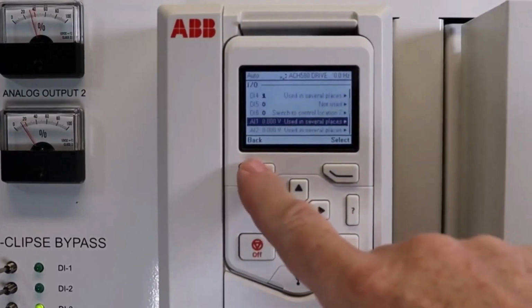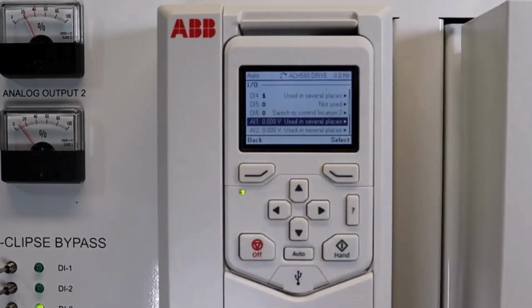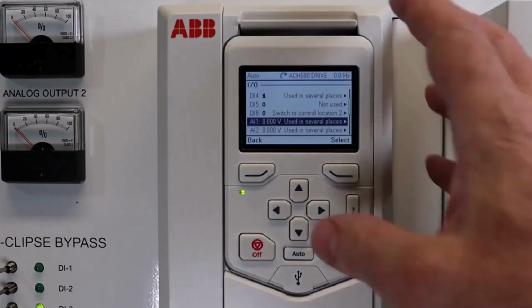But at this point, I can go, okay, I'm seeing 0 volts at the drive. I know the drive's programmed correctly because I put 5 volts into the drive by forcing it to 5 volts. The drive is following that speed reference. At this point, we need to troubleshoot the actual wiring and make sure it actually is getting the voltage that we expected to get for a speed reference. Of course, this would work in amps, milliamps, whatever we have set up for our analog inputs.